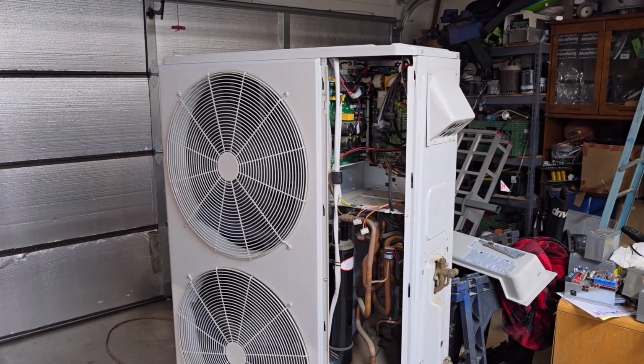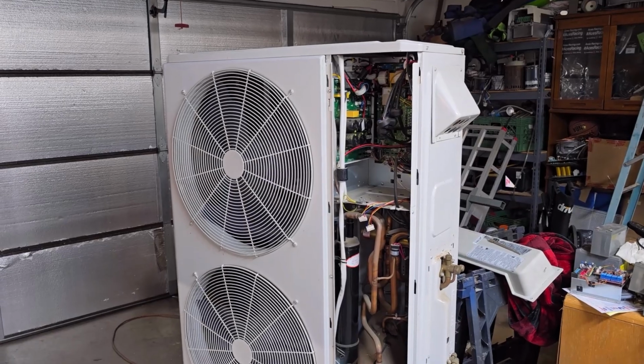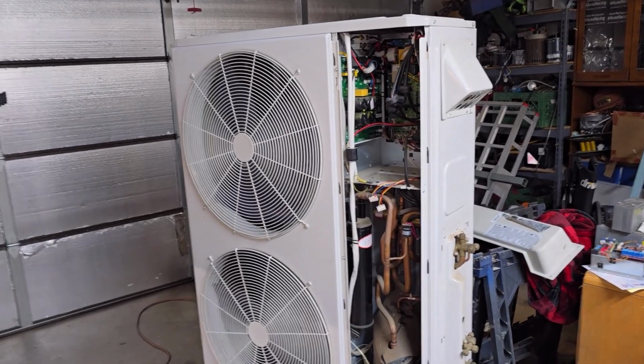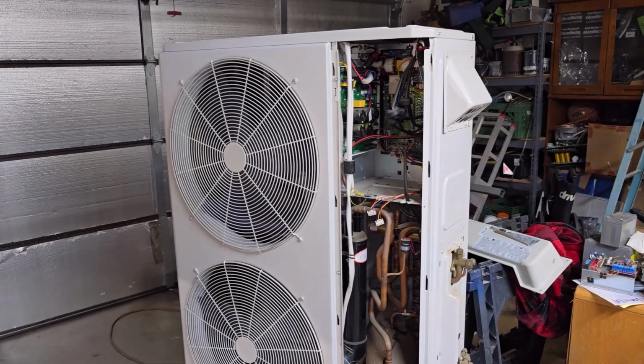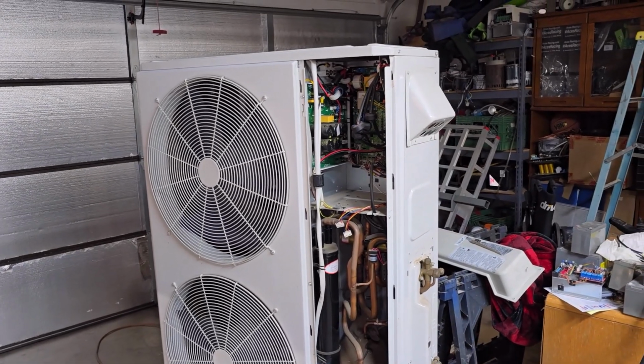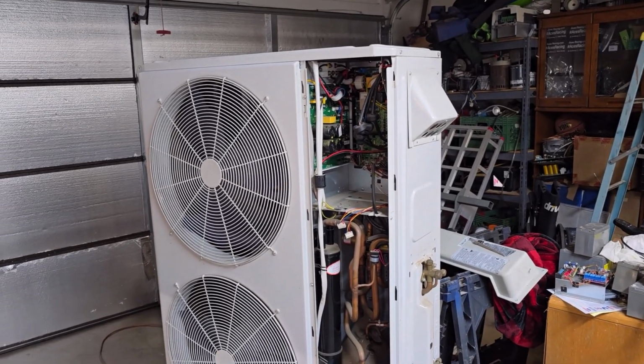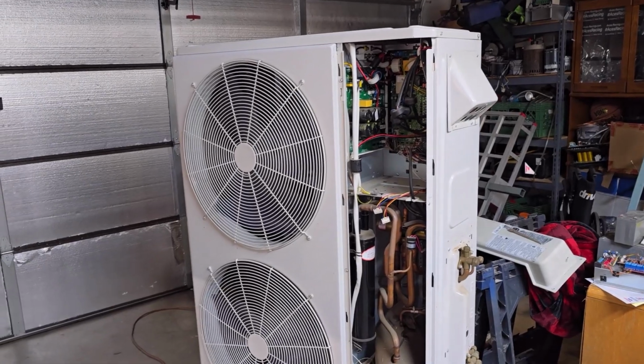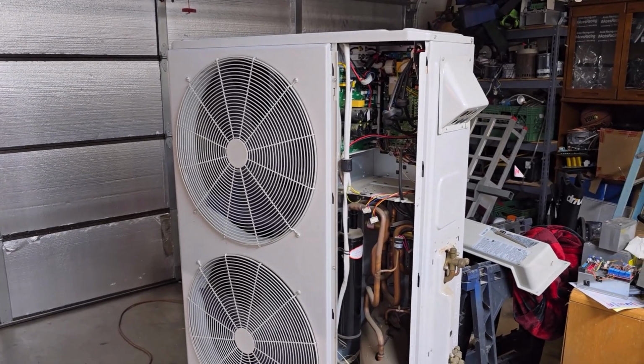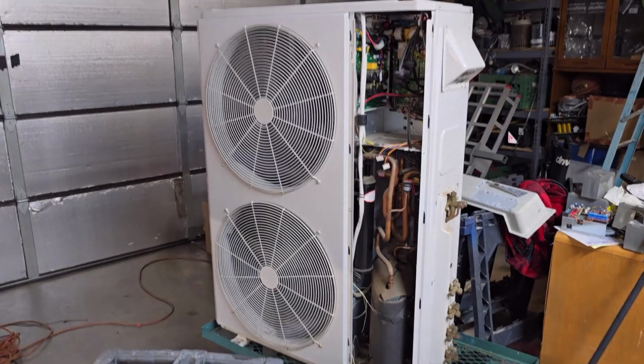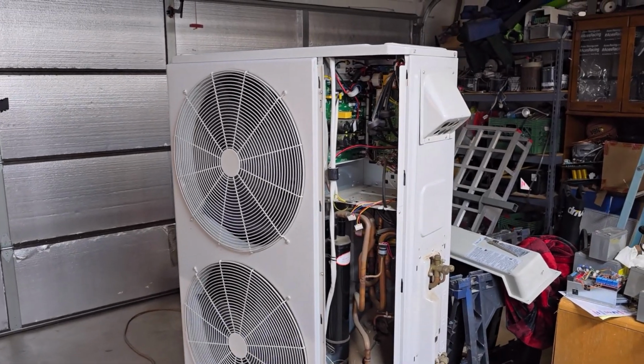The coil is a 3.5-ton, and I'm going to be hooking a 3-ton to it, so that should make the surface area about right, going from an old recip R22 to a newer 410 scroll system. You get a higher saturated coil temperature basically, so it should kind of work, and it'll be a nice little experiment.